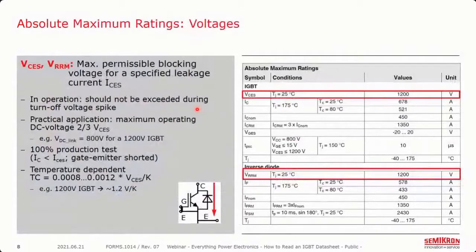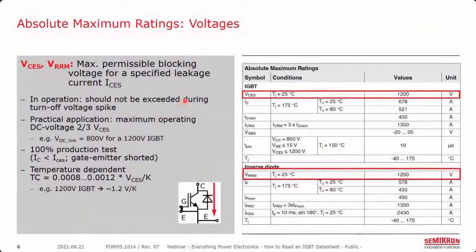Starting with maximum ratings and voltage, the first item at the top of the data sheet is the blocking voltage of the semiconductor — VCES for the IGBT and VRRM for the diode. This is a standard value across most power module manufacturers and serves as a way of broadly categorizing power modules, so we'll be talking about 600-volt, 1200-volt, or 1700-volt modules. This is defined as the maximum voltage the device can block in its off state or reverse state without exceeding a given leakage current, ICES, which is stated later in the characteristics section — for this IGBT, it's 5 milliamps.